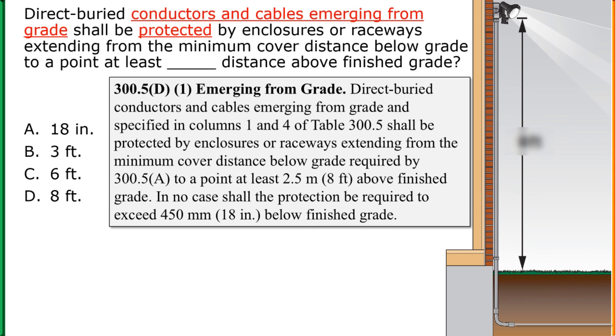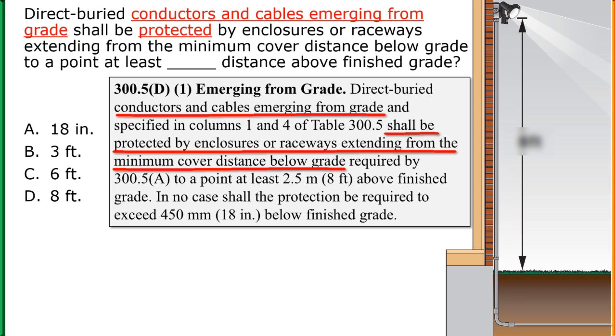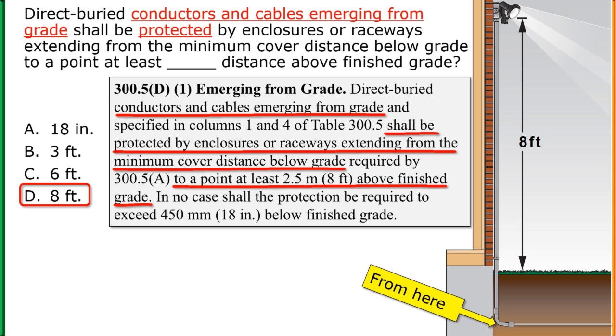When we go to 300.5D1, it tells us that direct buried conductors or cables emerging from grade need that protection by enclosures or raceways extending from the minimum cover distance below grade, which is here, up to at least eight feet above finished grade.